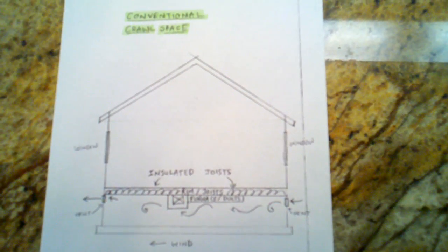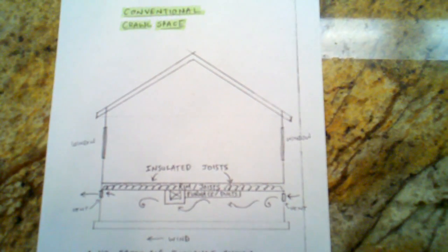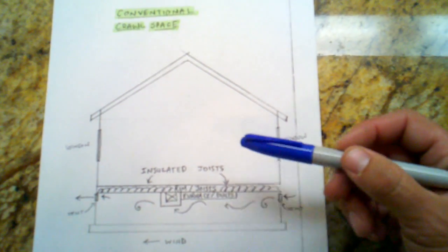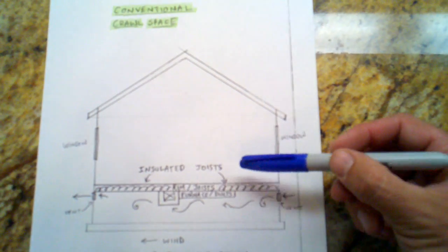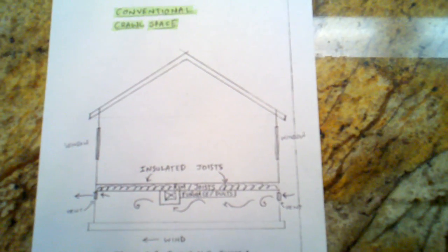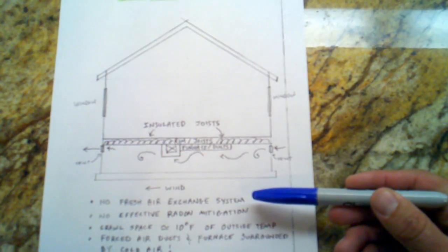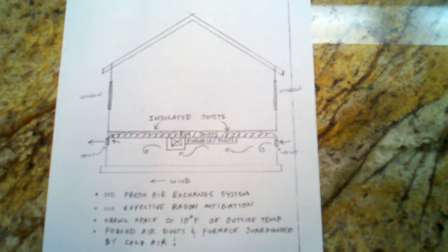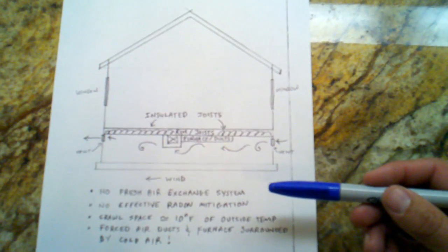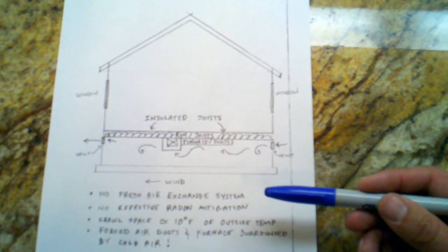And even with that insulation you will get cold floors where you have tile, especially. The temperature down below and the temperature up above, there's such a great difference that you will get that heat transfer even through insulation down into the crawl space. Big things: there's no fresh air exchange system, and when you build your homes as tight as we build ours, you really need a fresh air exchange system to bring fresh air into the house. It helps your indoor air quality greatly.